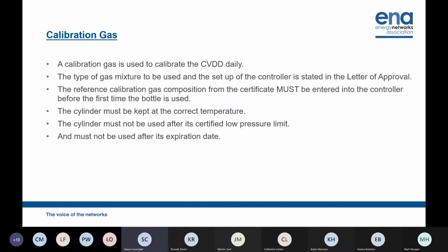Fairly sure we would trip. We would stop. I would hope you would. Yeah, your system should be set up so that if there are any problems, you would go to your divert valve or the ROV would close to prevent any gas flowing. That's okay. Thanks. But then again, if you don't change the calibration gas correctly, then you still end up with a loss of record. Yes, I understand that. Any deviation from the letter of approval, basically, that SGS determine should result in a loss of record, then they'll require that to be raised. Yeah. Okay, thanks. Okay, is that clear? Okay, so next slide.